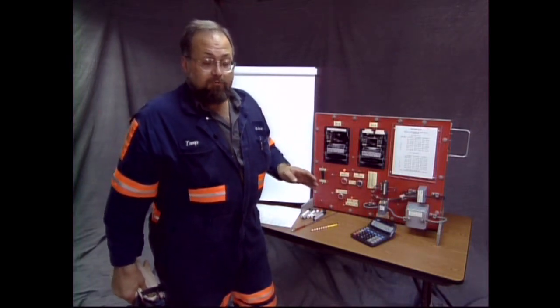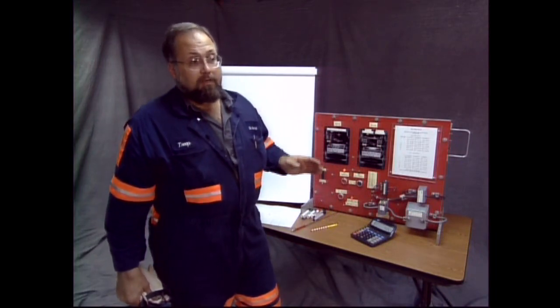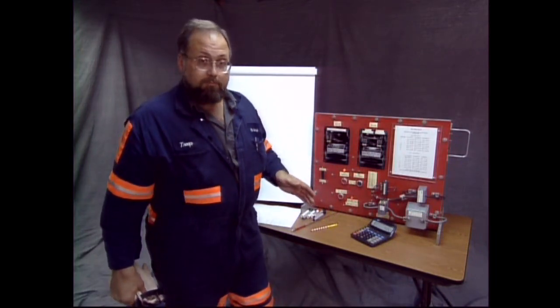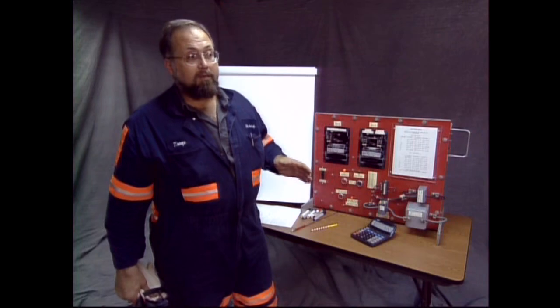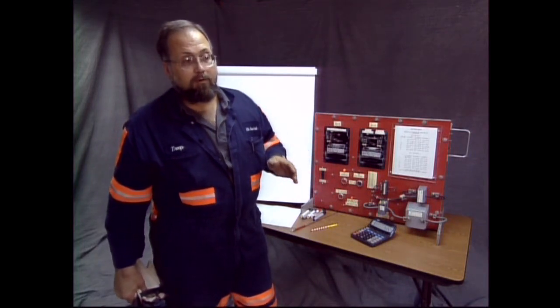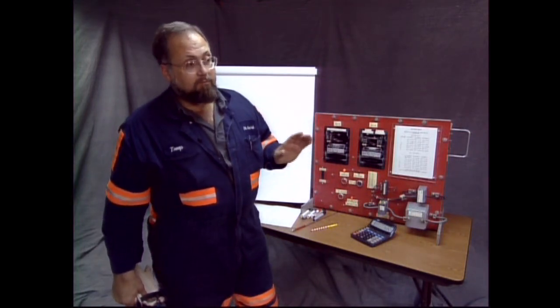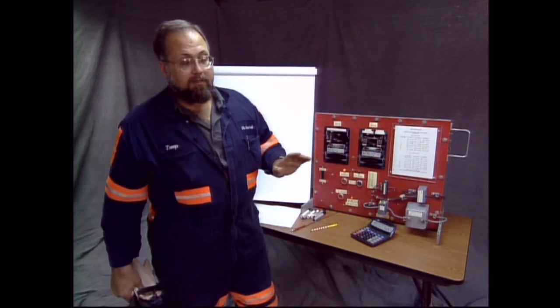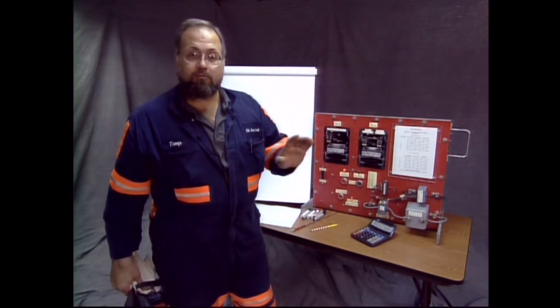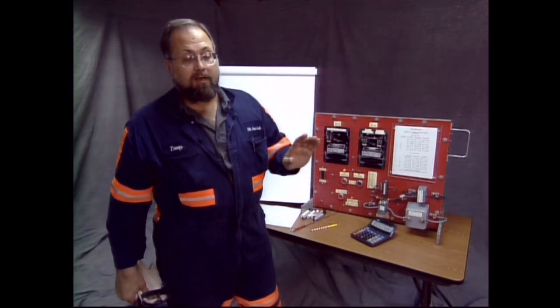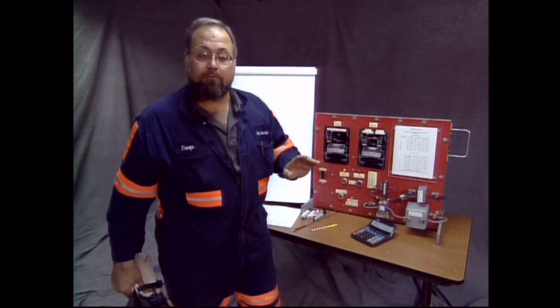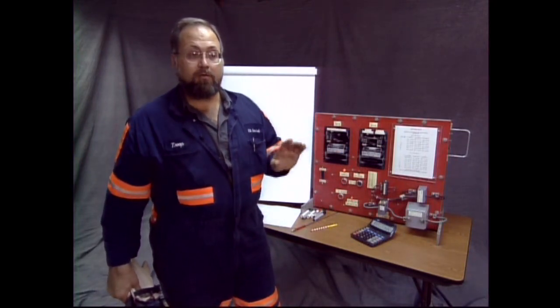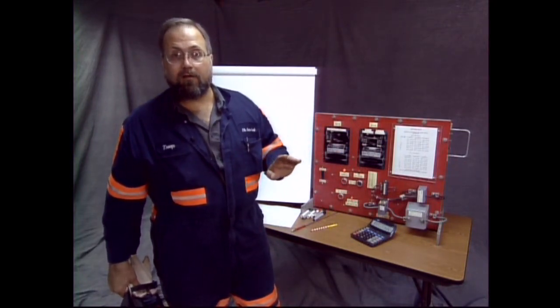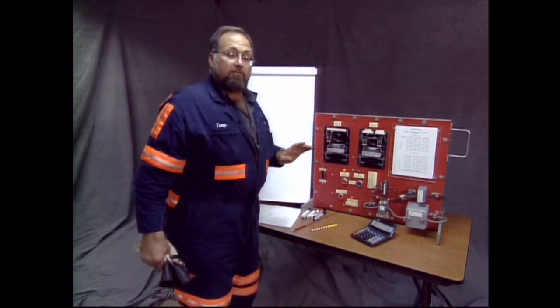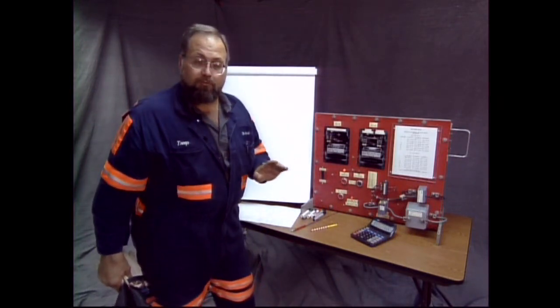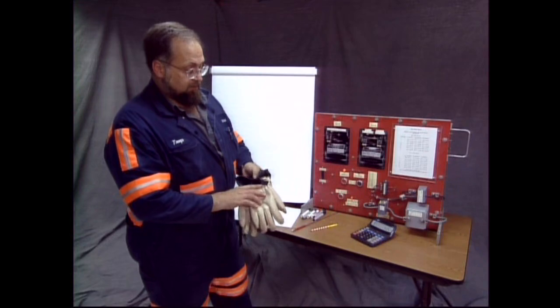At the next relay, you have a new ground monitor to take over that section of cable beyond this one. The end of the line is that point in your mind where from this relay, when you follow the cable to its end, it terminates in a box, in a transformer, and there's a high voltage input, but there's no feed through. The cable terminates, the high voltage circuit terminates at this point. That's the end of the line. One of those 2 places will be where you determine you have ground continuity to.